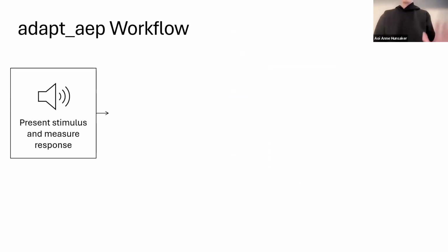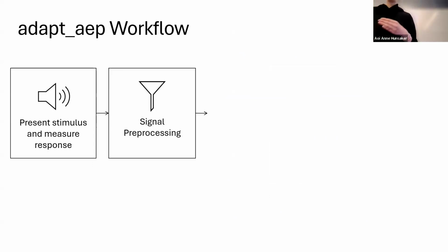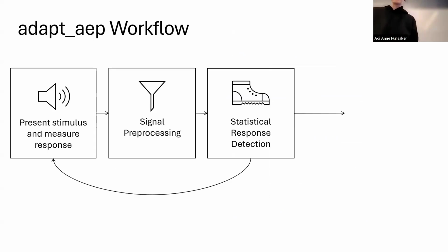So here is our proposed solution. In the ADAPT AEP workflow, the program will first present a sound over a speaker and measure the response from the electrodes. Then the signal from the electrodes will be filtered in order to improve signal quality. Then these signals are put through a response detection algorithm, and I'll go into detail about it next, where instead of an experimenter eyeballing the auditory response, statistical analysis is conducted to see if the response is statistically significantly greater than the background noise in the signal.